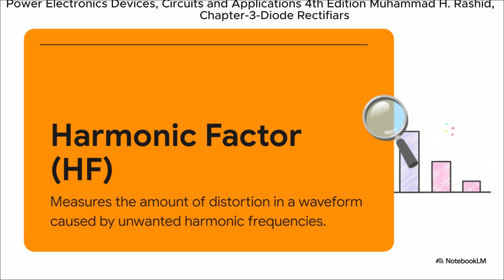A super important point to lock in: harmonic factor and total harmonic distortion, or THD, are just two different names for the exact same thing. They're a direct measure of the pollution on your waveform. So for a perfect sine wave with absolutely zero distortion, the THD is 0.